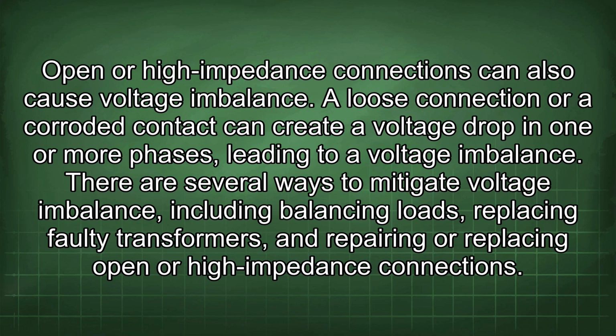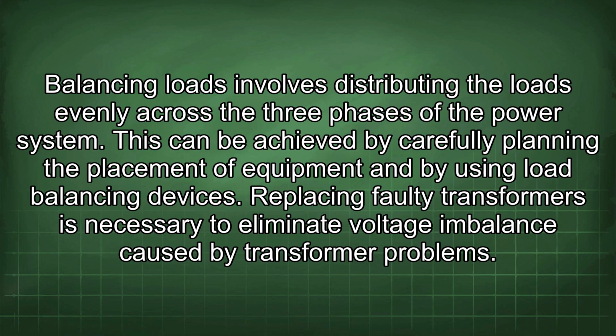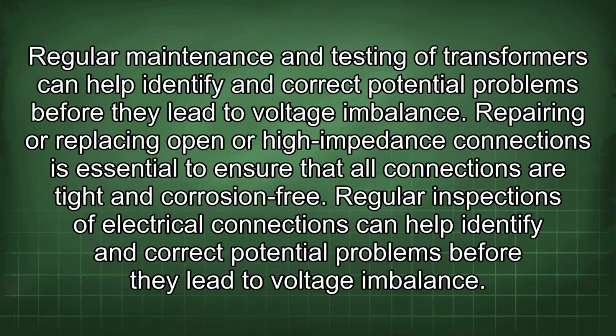or high impedance connections. Balancing loads involves distributing the loads evenly across the three phases of the power system. This can be achieved by carefully planning the placement of equipment and by using load balancing devices. Replacing faulty transformers is necessary to eliminate voltage imbalance caused by transformer problems. Regular maintenance and testing of transformers can help identify and correct potential problems before they lead to voltage imbalance. Repairing or replacing open or high impedance connections is essential to ensure that all connections are tight and corrosion-free. Regular inspections of electrical connections can help identify and correct potential problems before they lead to voltage imbalance.